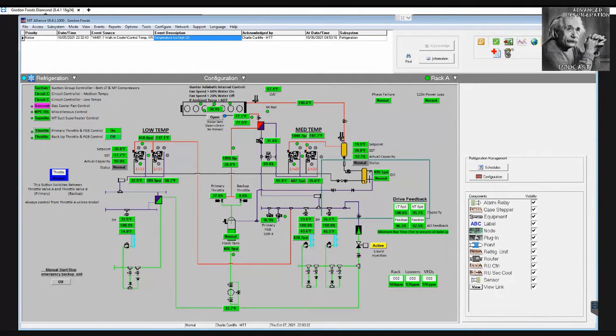And then again, it's got another valve that bleeds off to the low temp suction. So through the suction and through the drop, we're always trying to maintain as close to 100% liquid CO2 in the flash gas bypass at all times.